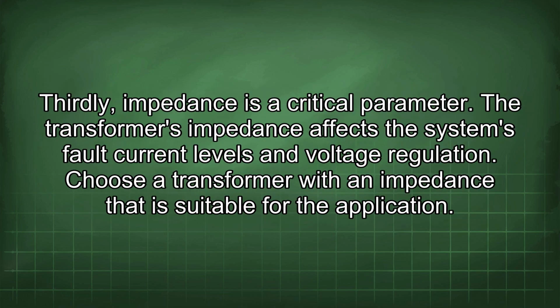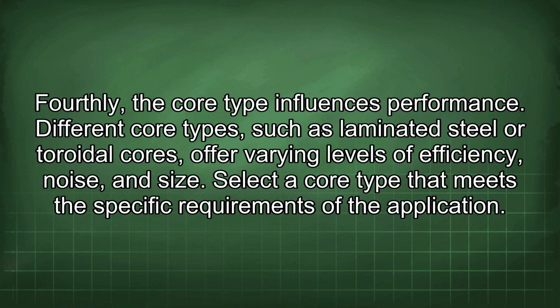Thirdly, impedance is a critical parameter. A transformer's impedance affects the system's fault current levels and voltage regulation. Choose a transformer with an impedance that is suitable for the application. Fourthly, the core type influences performance. Different core types, such as laminated steel or toroidal cores, offer varying levels of efficiency, noise, and size. Select a core type that meets the specific requirements of the application.